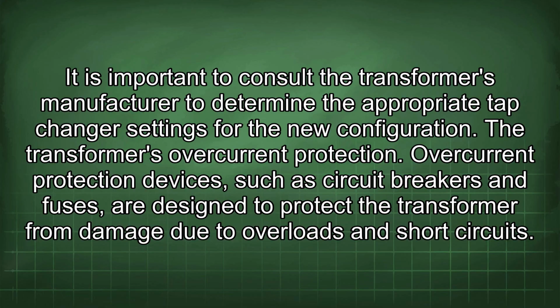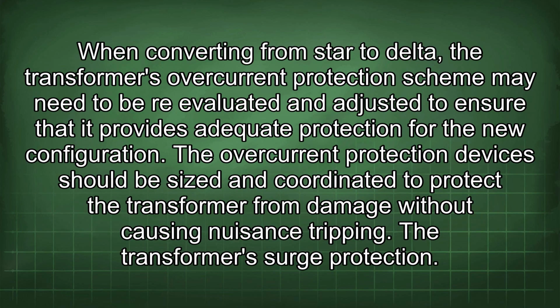The transformer's overcurrent protection. Overcurrent protection devices, such as circuit breakers and fuses, are designed to protect the transformer from damage due to overloads and short circuits. When converting from star to delta, the transformer's overcurrent protection scheme may need to be re-evaluated and adjusted to ensure that it provides adequate protection for the new configuration. The overcurrent protection devices should be sized and coordinated to protect the transformer from damage without causing nuisance tripping.